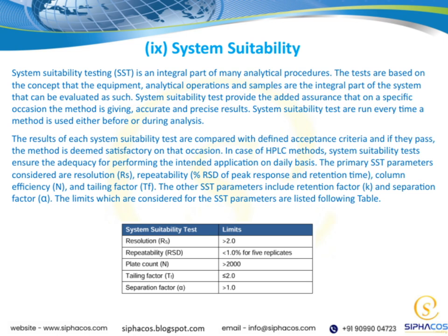The main purpose of conducting a system suitability test is to give us confidence that, on a specific day, our method is producing accurate and precise results. This isn't a one-time check. We run these tests every time we use a method, either before starting the analysis or during the process itself. When we perform an SST, we compare the results to predefined acceptance criteria. If the results meet these criteria, we can be assured that the method is satisfactory for that particular occasion.